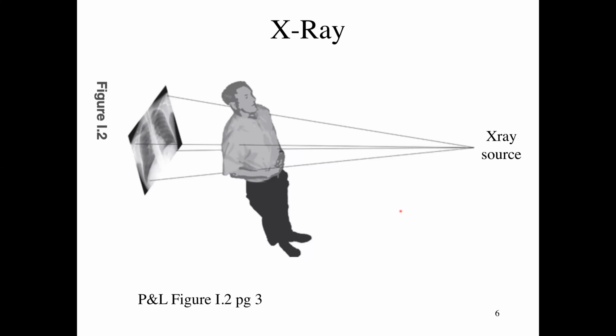In the modern case, we have an X-ray source, or say an X-ray flashlight. It's called an X-ray tube. It's about something this big, about the size of a loaf of bread, and it produces a beam of X-rays. X-rays come out of our source, and they pass through the patient and hit the detector. And the detector traditionally has been a phosphor screen that flashes, and then you put film behind that and you expose the film.